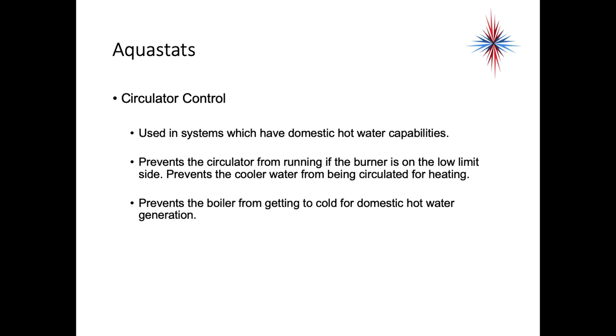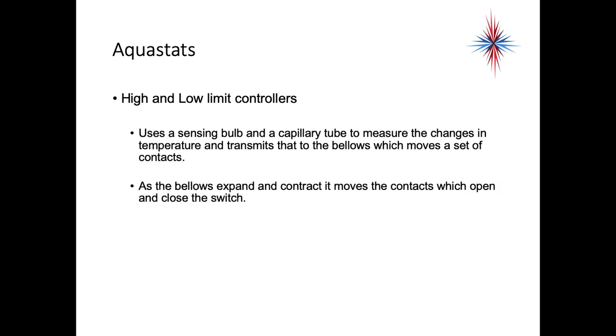We have to maintain boiler temperature for domestic hot water. The aquastat also includes circulator controls, used in systems which have both domestic hot water capability. It prevents the circulator from running if the burner is on the low limit side, prevents cooler water from being circulated for heating, and prevents the boiler from getting too cold for domestic hot water generation. This type of aquastat uses a sensing bulb and a cap tube to measure temperature changes and transmit that to bellows, which move a set of contacts — as the bellows expand and contract, the contacts open and close a switch.